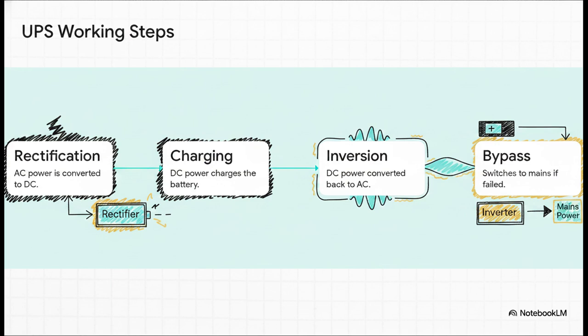Let's look under the hood at the mechanics, specifically focusing on the gold standard, the online double conversion UPS. This system sequentially scrubs dirty power in such a fascinating way. First up is rectification. It takes the incoming, messy AC power from the wall and converts it into pure DC power. Second is charging, where that DC power is used to constantly top off the internal battery bank. Third is inversion. The system takes that DC power and converts it back into a pristine, regulated AC sine wave to feed your equipment. It's literally double converting the power to clean it. And fourth is the bypass. This is a static switch that safely moves the load back to raw mains power if the UPS's internal components ever suffer a failure, so you never go dark.